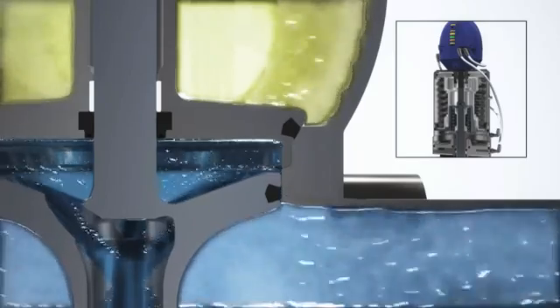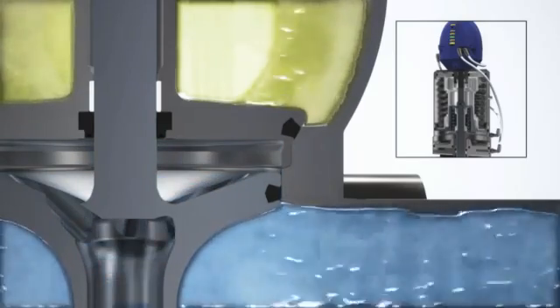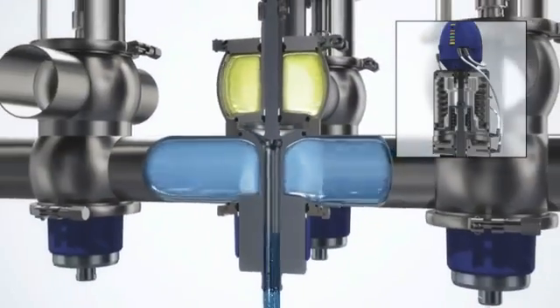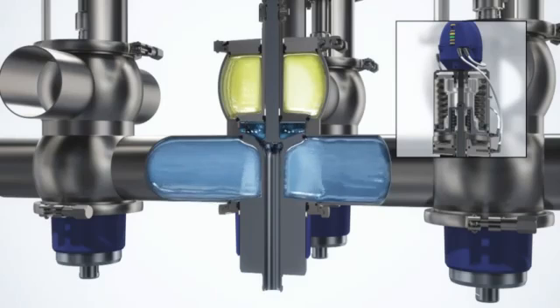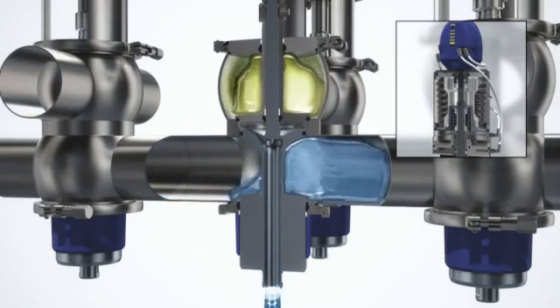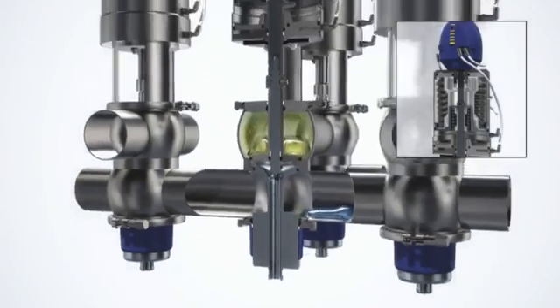It also reduces pressure of the CIP fluid and promotes risk-free cleaning because there is no risk of pressure build-up in the leakage chamber. It is important to adjust the duration of a seat lift or seat push operation to match the requirements of the process and product.